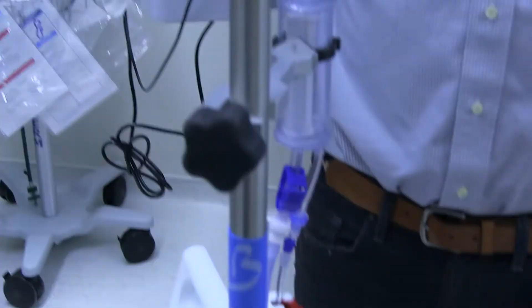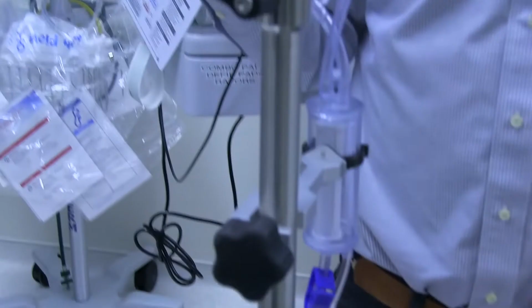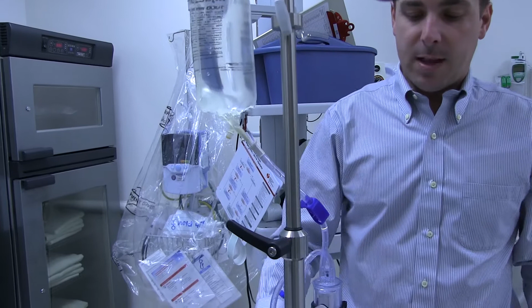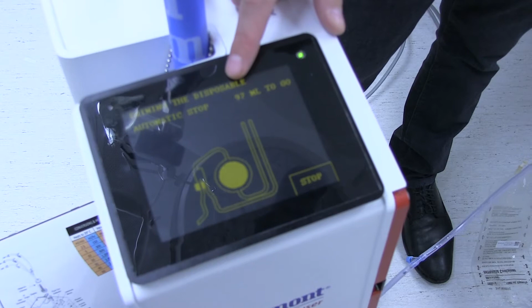So out of the box, all the lines come open. So I usually say clamp off the bifurcated set, save that for the blood, and then follow the prompt. Connect fluid bag, unclamp line, press prime, do it again. So grab a saline. Once you get a little fluid in the reservoir, you can press prime, and it starts a 100 countdown. It's clamped off internally here to the patient line.